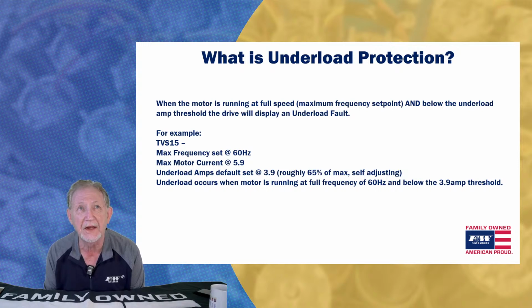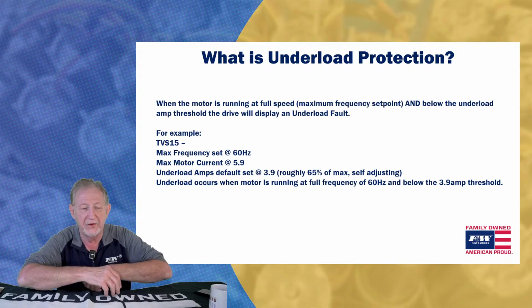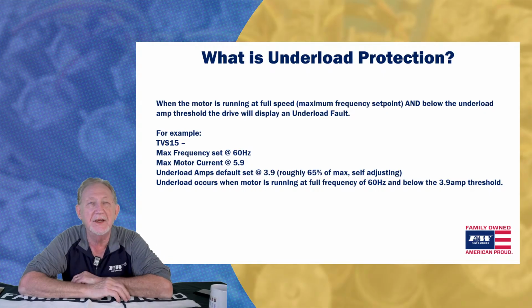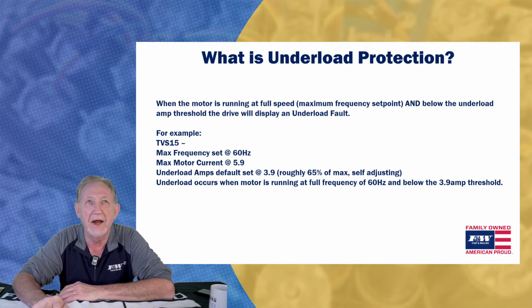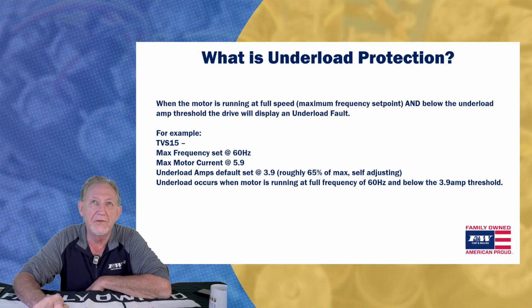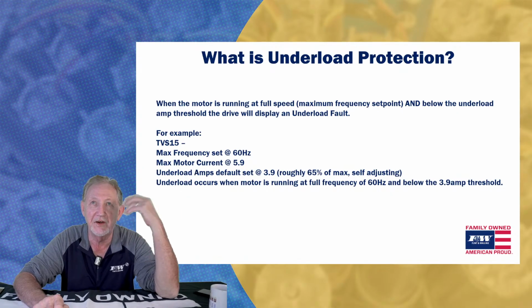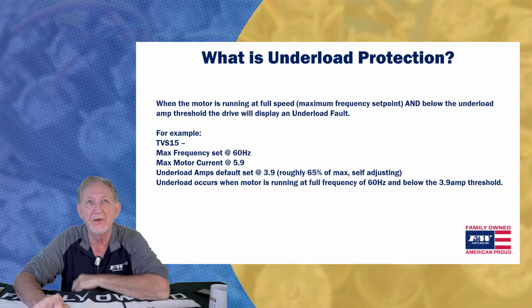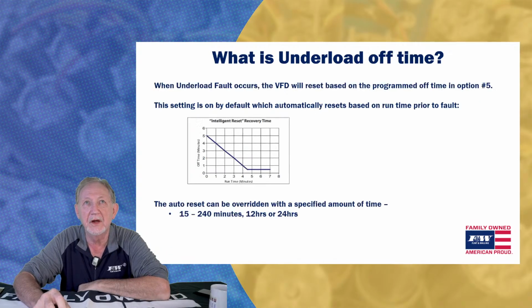That's going to default. So every time you change that max motor current by horsepower, it's also going to automatically change that default underload amp setting, all right? Underload is going to occur when that pump is running at full frequency, 60 hertz, and below that 3.9 threshold. That's when an underload is going to occur.